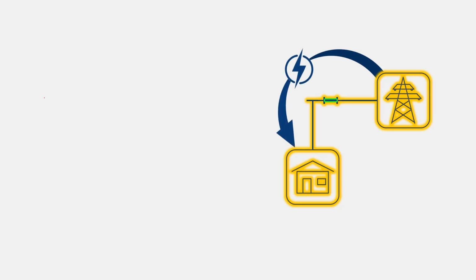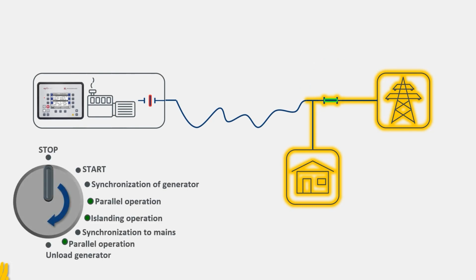Initially, a utility provides power for the village, which is the load. We start the engine. The engine runs up to the desired speed and voltage. Especially in cold climates, the engine needs to reach its operating temperature before the generator breaker gets synchronized. There is a fixed generator and busbar measurement inside the generator switchboard.